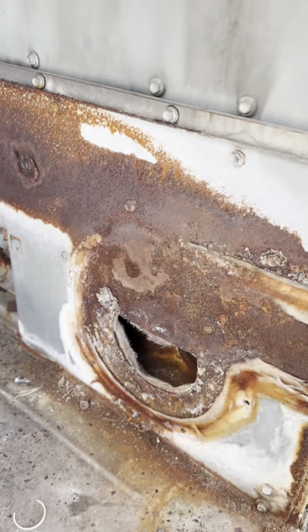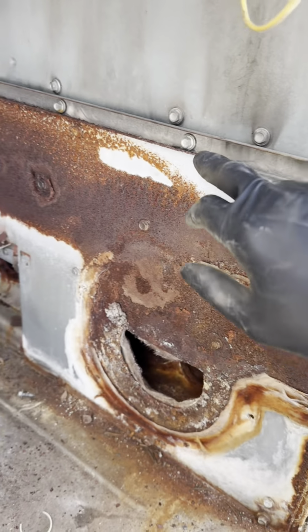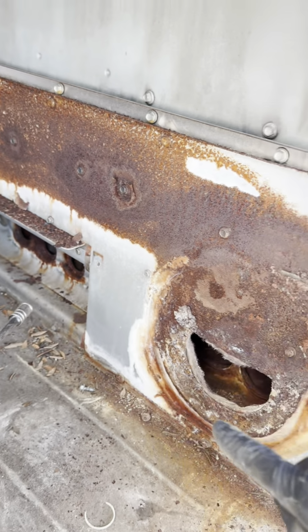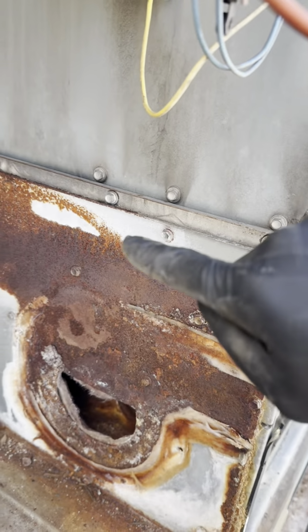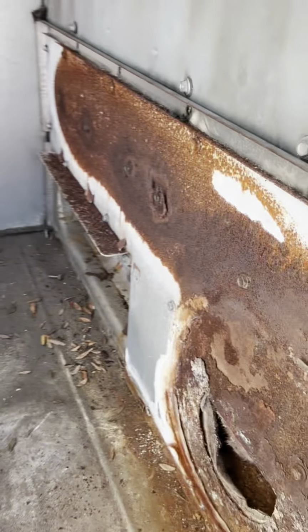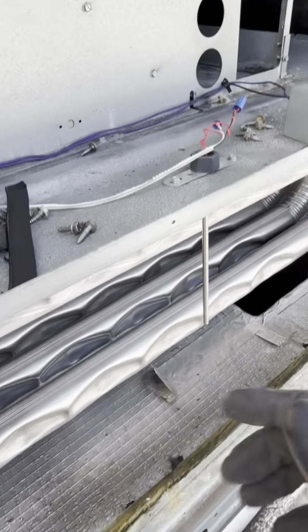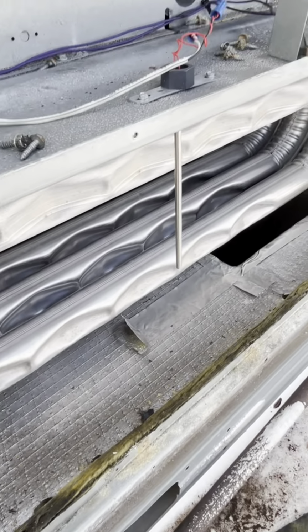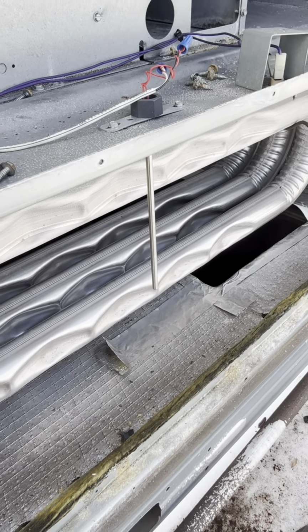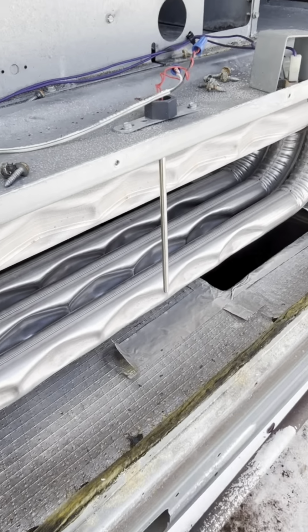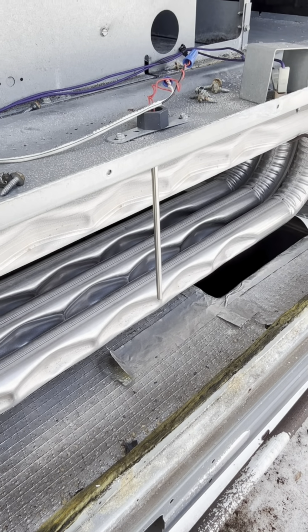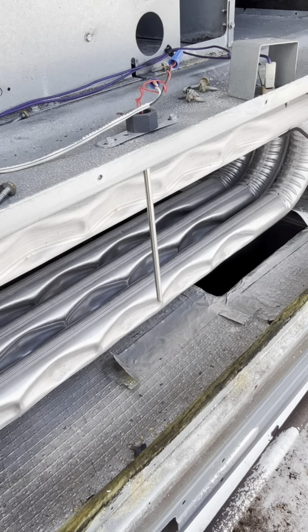Back in the front, remove all the support screws that are supporting the heat exchanger, all the way around, so we can slide the heat exchanger out. The screws are removed. Now I have to remove this BAS discharge sensor that is in my way, kind of. Typically, this is not there unless your building is supplied with a BAS.